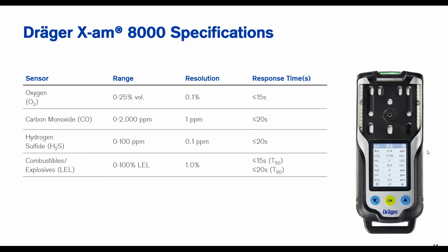But you can look at this, and this is where you get those T90 response times, those T50 response times, understanding the range that it actually works in, and then how small of a resolution it will actually go down to. So look at this particular meter, the one you see on the right. Your oxygen sensor on that particular one will read from 0 to 25% oxygen in 0.1% resolution. Typical response time at T90 on that is less than or equal to 15 seconds. It may be 15 seconds, it may be 3 seconds, just less than or equal to 15 seconds.